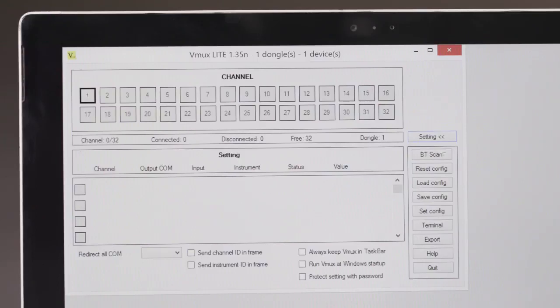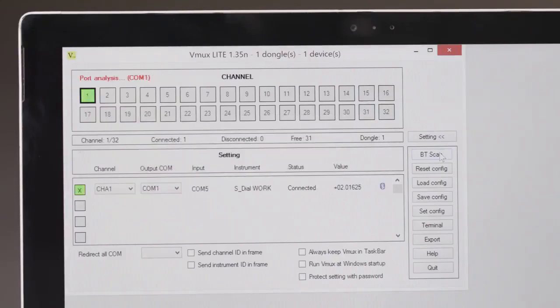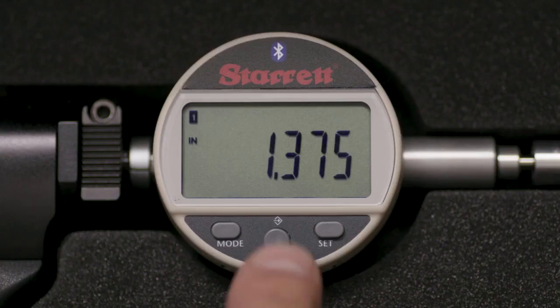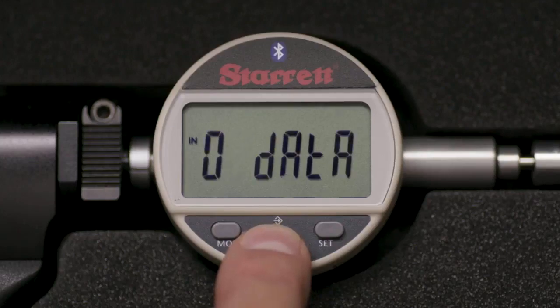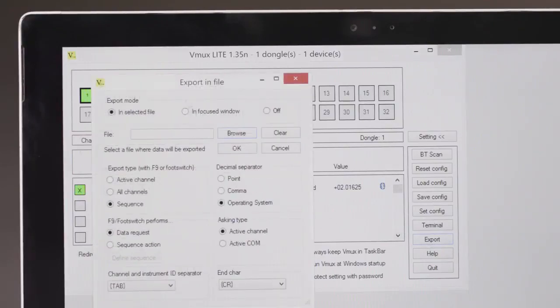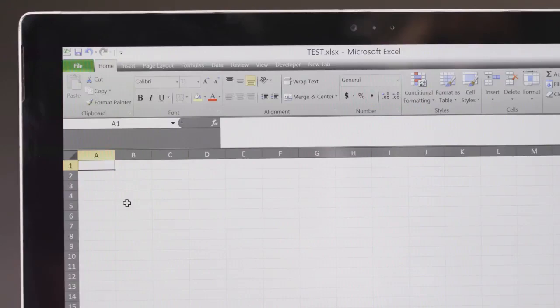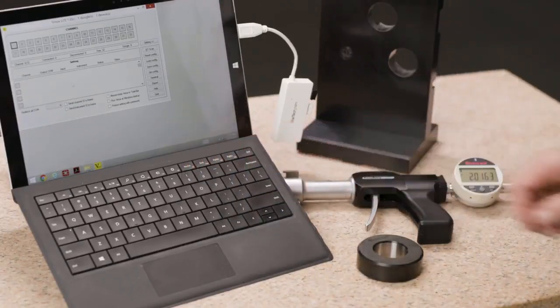In vMux, press BT SCAN. Once detected, the tool will appear on a list and the Accubore Bluetooth icon will be ON. The tool and PC are now connected via Bluetooth. If you wish, set your MIDDLE or FAVORITES button to ZERO DATA. For our demonstration, we will send data to an Excel file. Select EXPORT from the vMux main screen — the EXPORT screen will open. Select IN SELECTED FILE and ACTIVE CHANNEL, then browse to select the destination file on your PC and select OK to open the file. Tap the MIDDLE button to send the screen value to the selected cell; press again and that value will appear in the next cell. Alternatively, data can be sent by pressing F9 on the keyboard or with a footswitch.